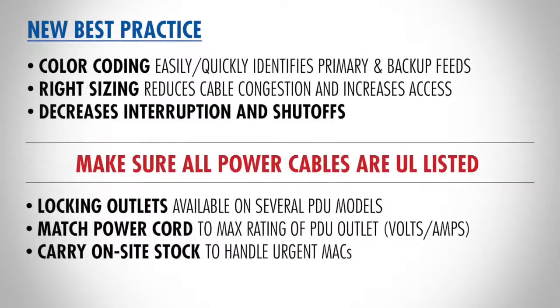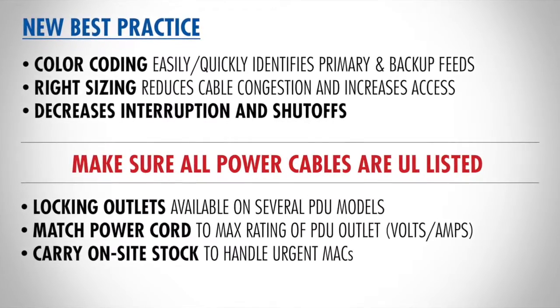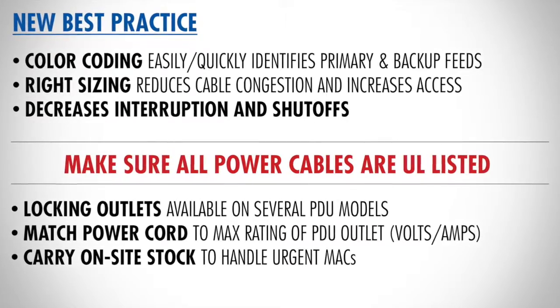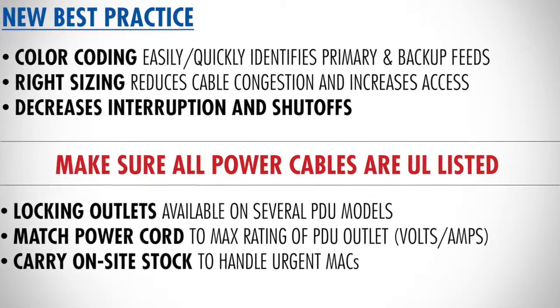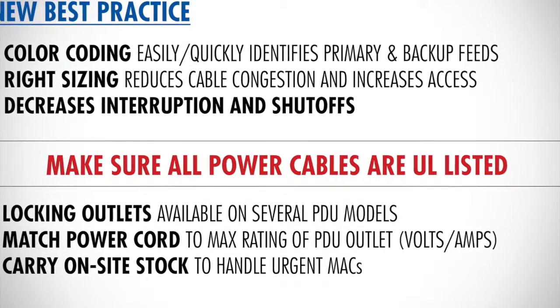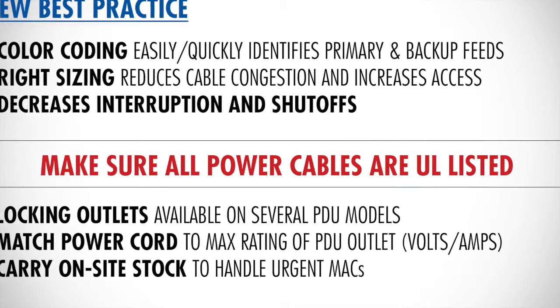And of course, it's very important to keep our servers and switches and devices in the data center powered up and breathing. What's quickly becoming a best practice today is use color coding of your PDU power connections. One of the major advantages of doing this is going to allow you to easily differentiate between your primary and secondary power feeds from the PDUs into your dual-ported devices. Almost all servers and switches have redundancy when it comes to power supplies, so it allows you to show your A and your B feeds.